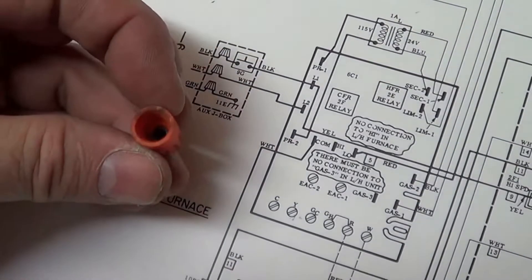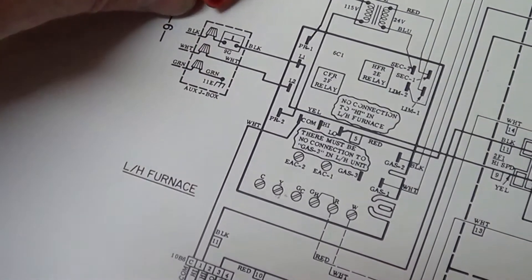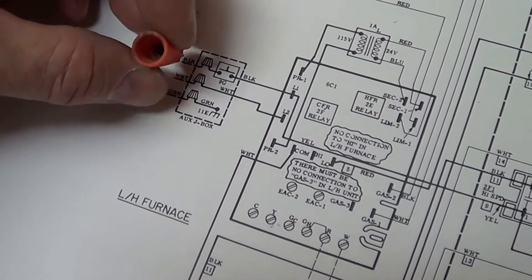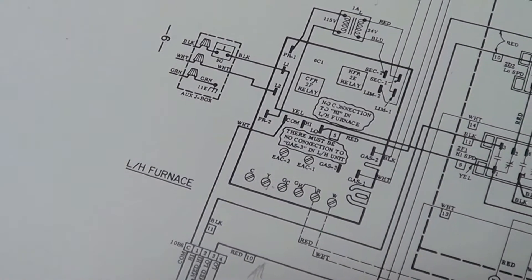There it is, the wire nut. The wrong wire nut was put on here years ago back in '85 and it finally let loose. It wasn't properly engaged and I spent probably an hour trying to figure out what was wrong with it. That's what this tale is about.